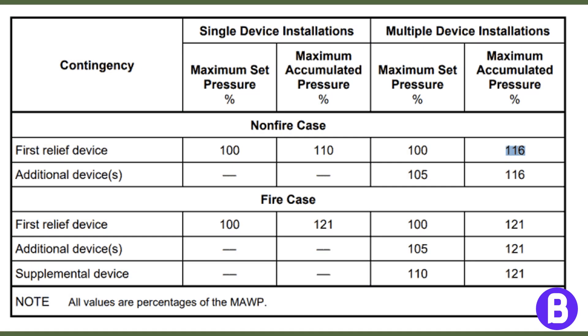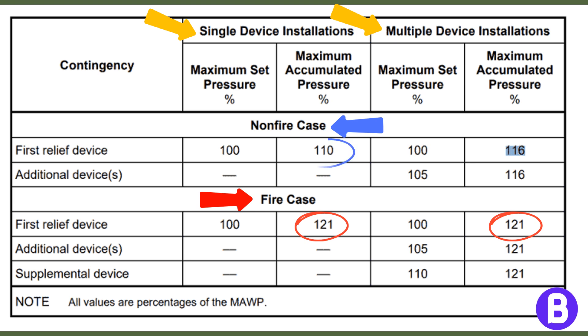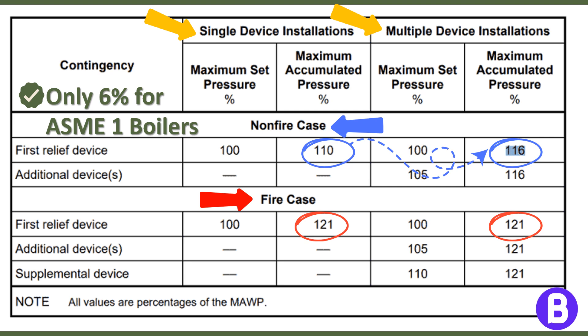From this table, API 520 shows the overpressure limits for single and multiple installations of a pressure safety valve. For the fire case, ASME Section 8 designates the pressure accumulation limit to be 121% of the vessel's maximum allowable working pressure. For other overpressure cases, the accumulation limit is 110% for single valves and 116% for multiple valves. For ASME Section 1 coded boilers, the accumulation is even more stringent, as only 6% overpressure is accepted.